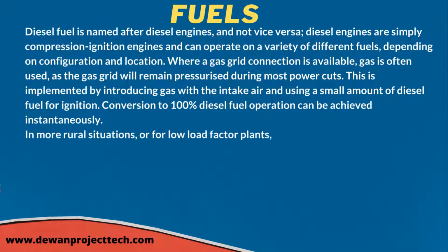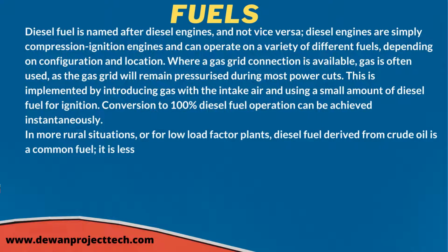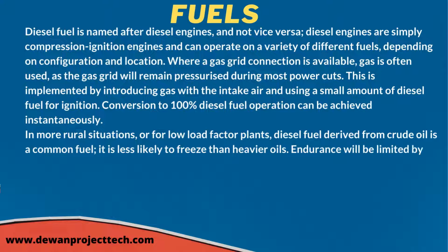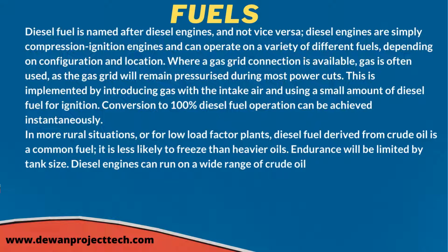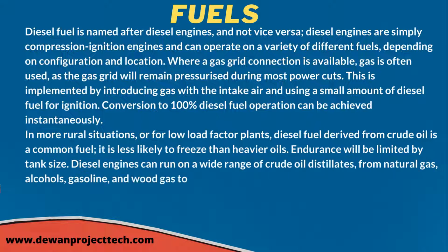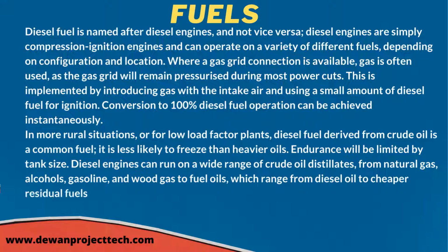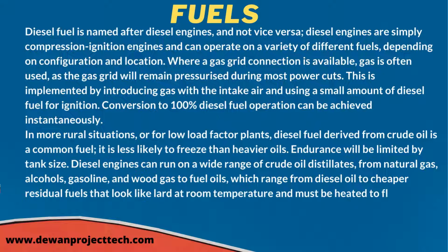Diesel fuel derived from crude oil is a common fuel. It is less likely to freeze than heavier oils. Endurance will be limited by tank size. Diesel engines can run on a wide range of crude oil distillates, from natural gas, alcohols, gasoline, and wood gas to fuel oils, which range from diesel oil to cheaper residual fuels that look like lard at room temperature and must be heated to flow down a fuel line.